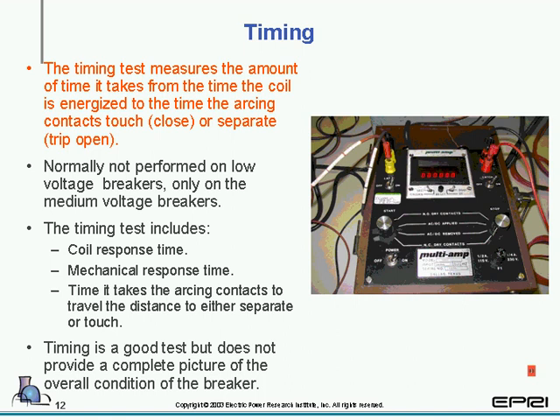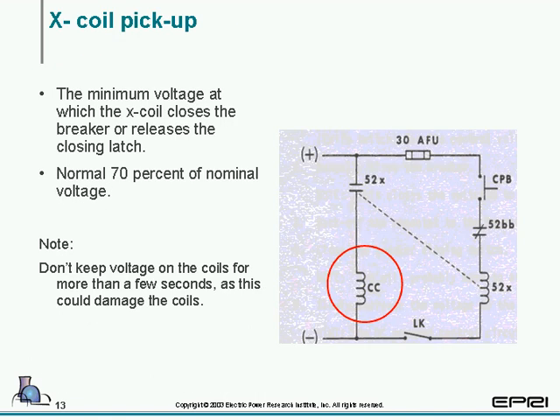The timing test only tests certain components in the breaker. It does not give you a complete picture of the overall condition of the breaker. It doesn't tell you anything about the arc chutes and other parts of the operating mechanism and so forth. So it's just one window, one tool in your tool bag.